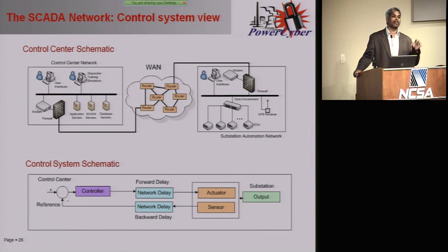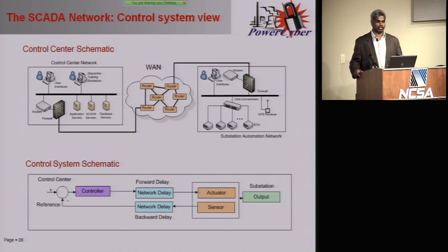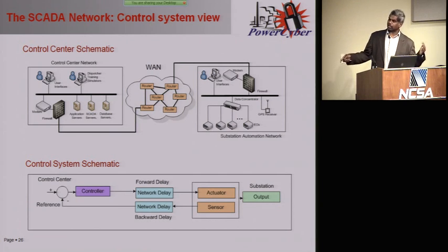I want to emphasize the SCADA control system is a control system, not an IT system. Control systems have dynamics, feedback loops, and timing requirements for communication and control. From a control-theoretic perspective, you have a plant, the power system, to be controlled. The plant has sensors and actuators: the sensor senses something and sends it to the controller, which makes a decision, and the controller then actuates the physical system, and so on.